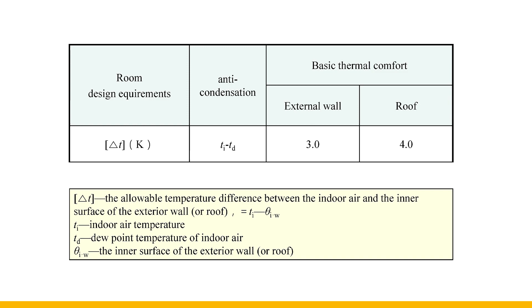The thermal performance of the enclosure structure can be tested by using the calculation formula of the minimum heat transfer resistance. For a new building, the form of the external enclosure structure needs to be reselected if it is not satisfied. For an existing building, an insulation layer needs to be added if it is not satisfied. The insulation thickness can be determined by calculation.